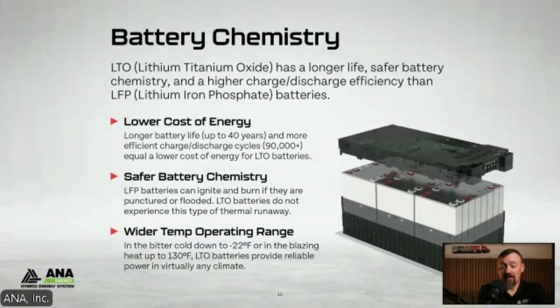Safer battery technology: LFP batteries have a tendency to hit a spot, if not handled and cooled correctly, where they can hit a thermal runaway event. And when you hit a thermal runaway event with LFP, it generates its own oxygen, so it's very difficult to extinguish once it has started on fire. That's another large benefit to LTO technology - it really can't experience that type of thermal runaway. So if something does light on fire, it's a lot easier to extinguish.